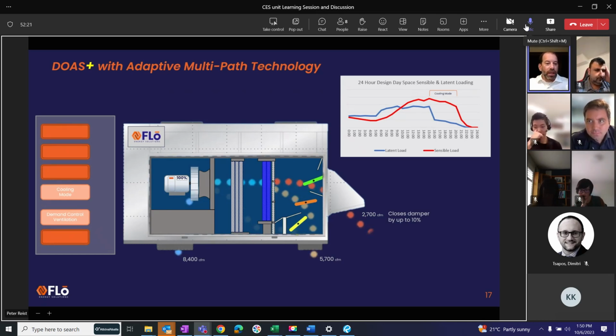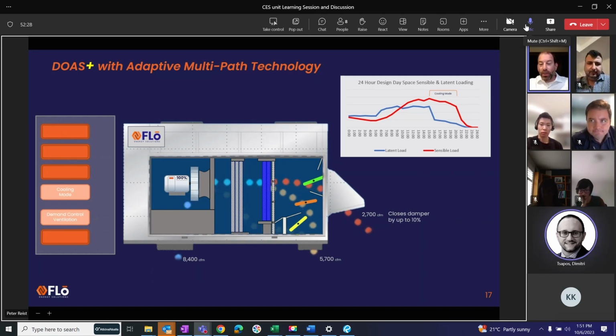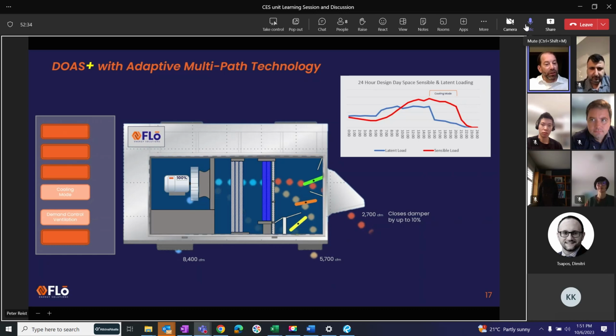One thing to point out: we're showing the dynamic nature in the course of a day, but this dynamic nature exists across different seasons too. Your wintertime won't have humidity, but your summertime will. Your shoulder seasons will be different. Different regions across North America experience the same kind of variation. Put this unit in the desert, it's never going to be in dehumidification mode, it's always in cooling mode. Put it anywhere on the eastern coast or down to Florida, it's always going to be in dehumidification mode, or at least whenever that matters.